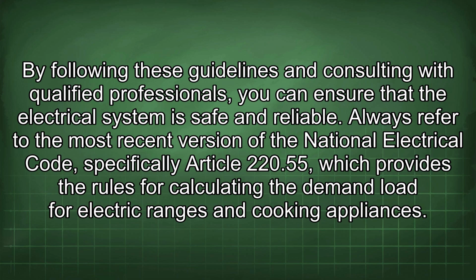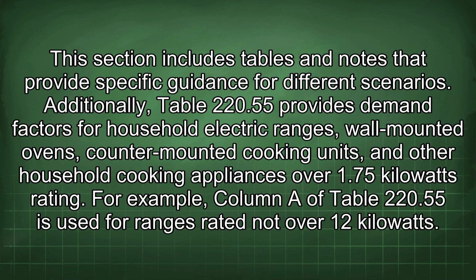Always refer to the most recent version of the National Electrical Code, specifically Article 220.55, which provides the rules for calculating the demand load for electric ranges and cooking appliances. This section includes tables and notes that provide specific guidance for different scenarios. Additionally, Table 220.55 provides demand factors for household electric ranges, wall-mounted ovens, counter-mounted cooking units, and other household cooking appliances over 1.75 kilowatts rating.